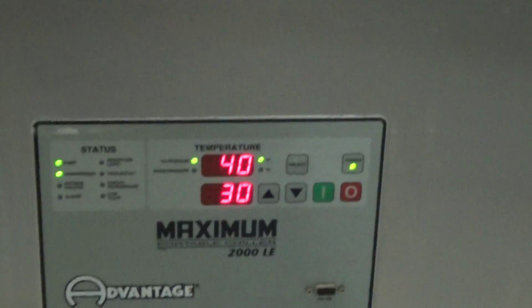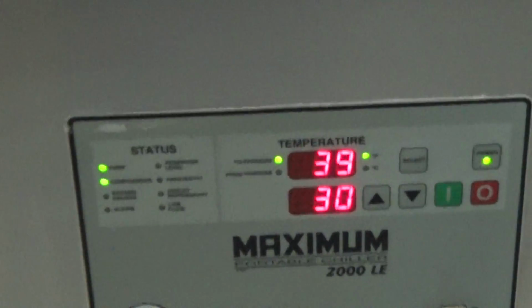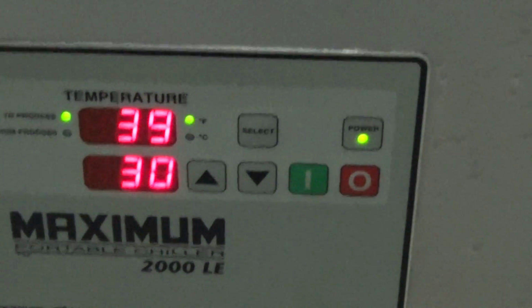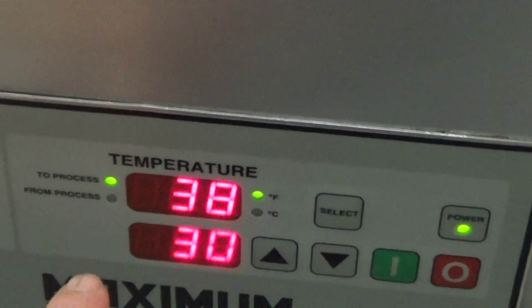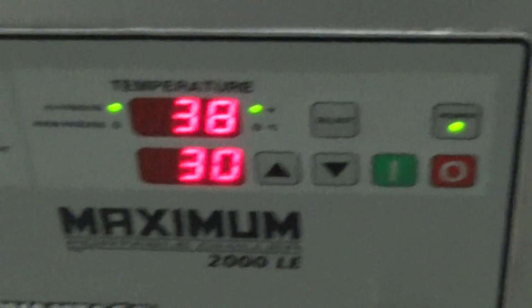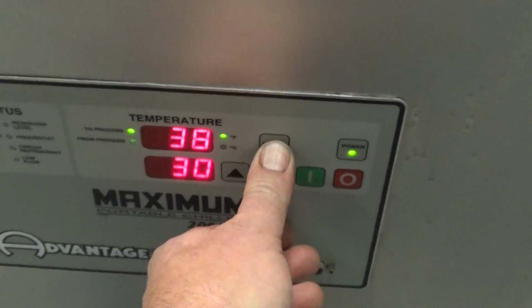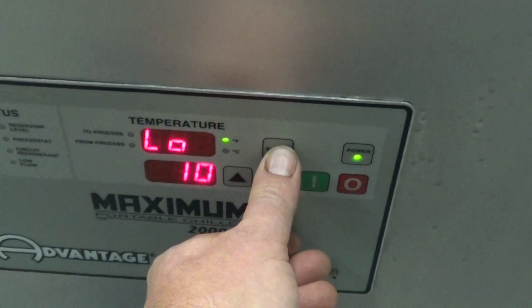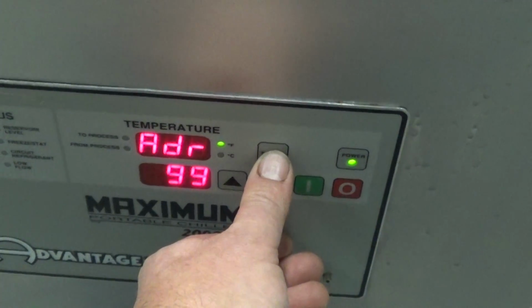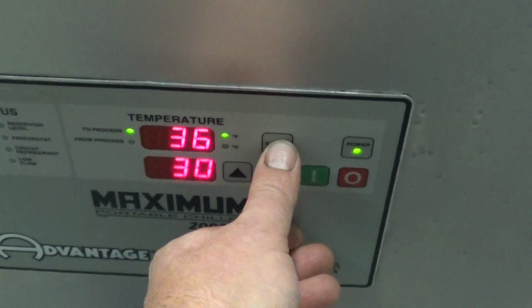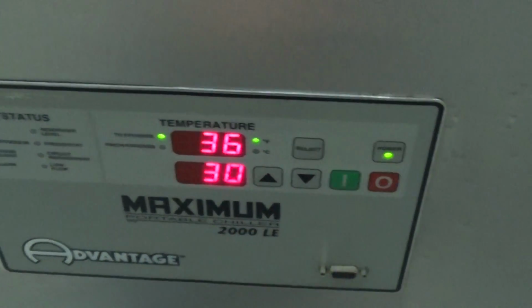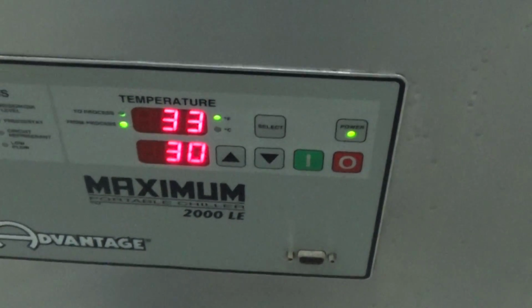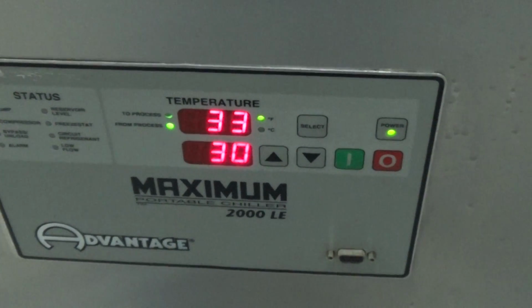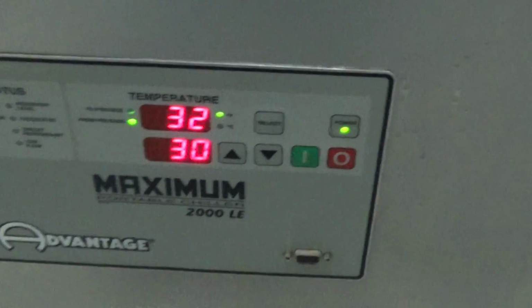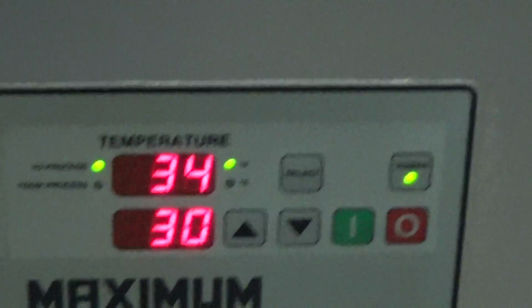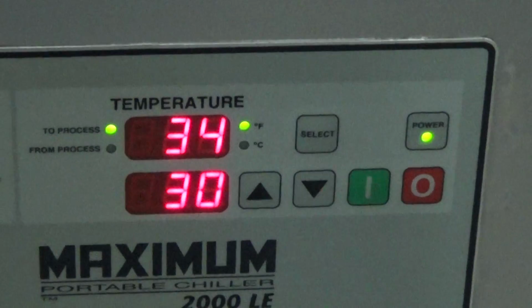So we're at about 40 Fahrenheit now, and this is set up so you have the option, inspection-wise, to look at both to process temperature and from process temperature. Right now the controller is kind of in technician mode, so we have a bunch of options that our technician can check, like high pressure safety cutout and so forth. We'll change that before it ships, so the main thing you can adjust is the set point. But right now, as you can see, the from process is 33 Fahrenheit. That'll default back to the to process temperature momentarily. And we have it set up for Fahrenheit.